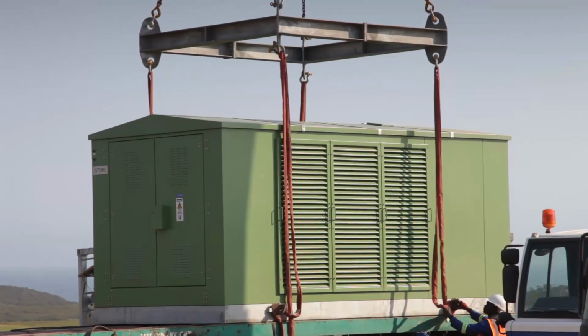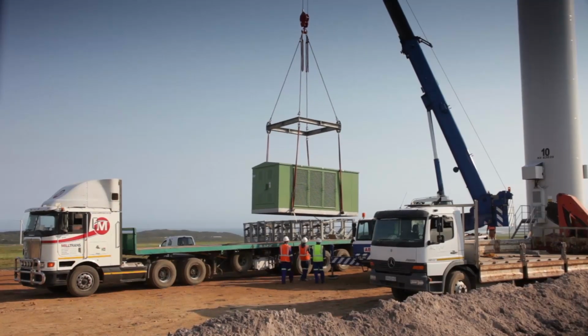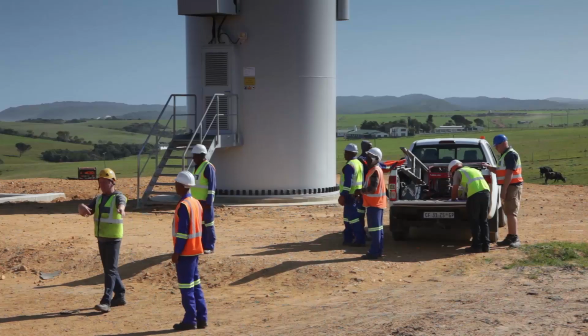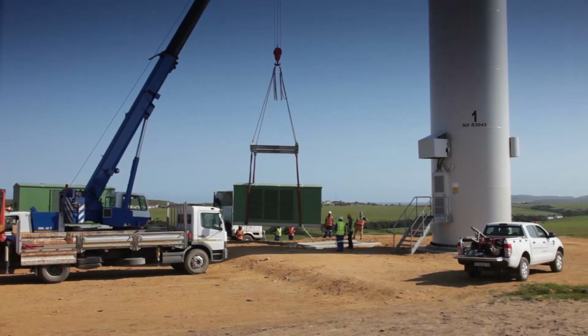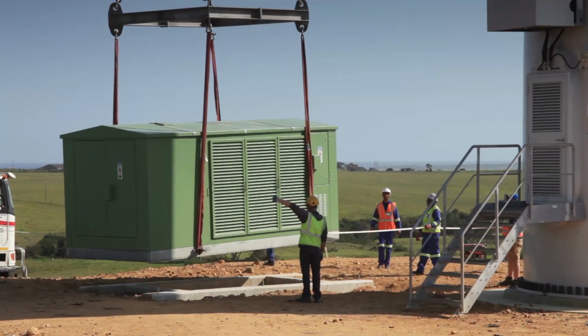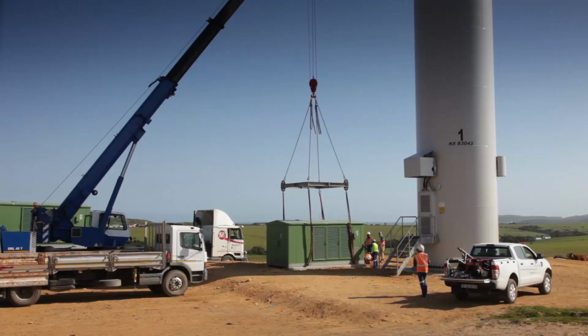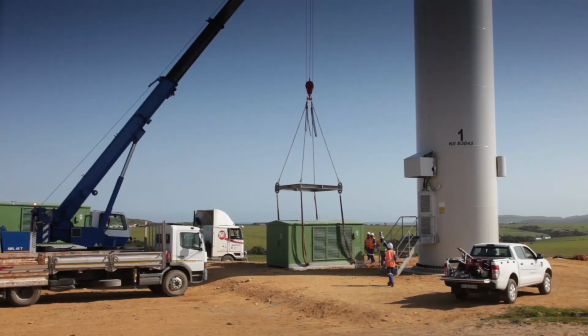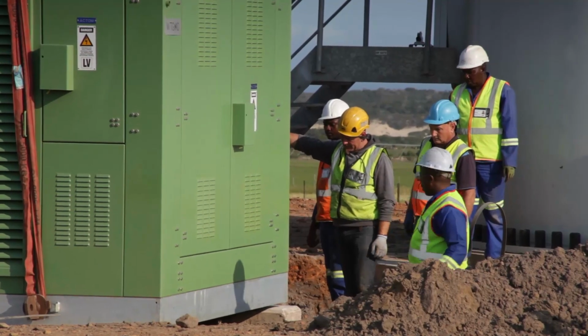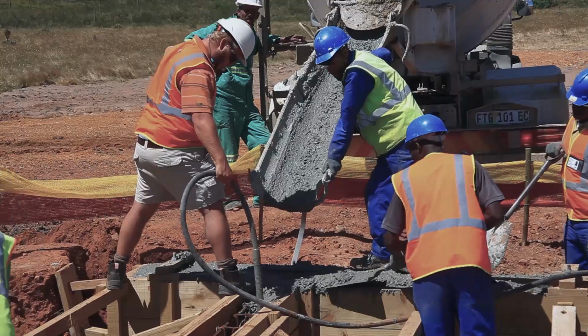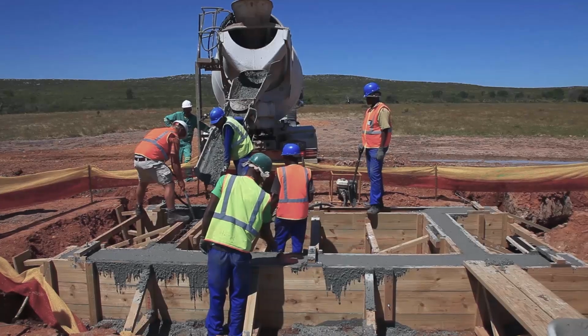The pad mount transformer kiosk is installed at each wind turbine. It contains the medium voltage switchgear and transformer required to control and increase the turbine output voltage to 33 kilovolts. The kiosk is mounted on a concrete foundation specially built to accommodate and support the weight of the equipment.